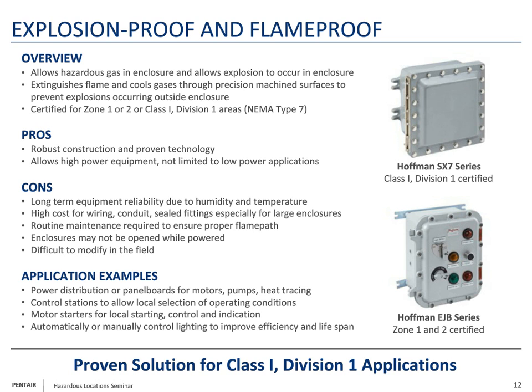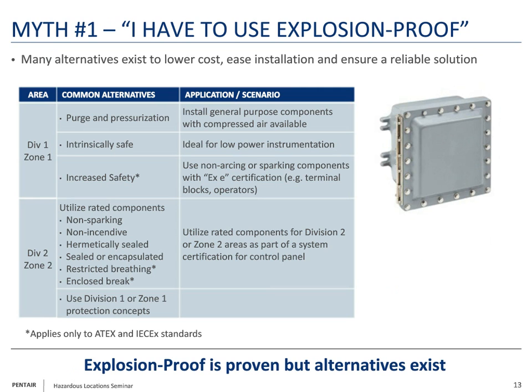One of the most common myths that we hear from customers is, I have to use an explosion-proof enclosure in a hazardous area. The point is that explosion-proof is proven and has a great use case, but you do have alternatives. With purge and pressurization, you can install general purpose components into a hazardous area, and you have to have compressed air available. If you have that available to you, that might be a good alternative, especially for large control panels.